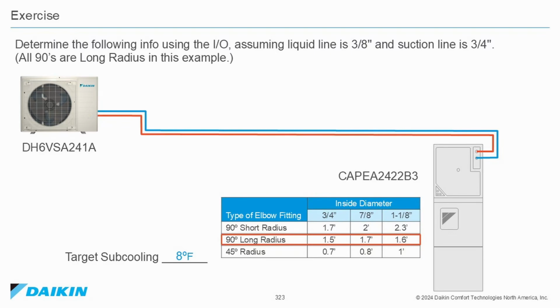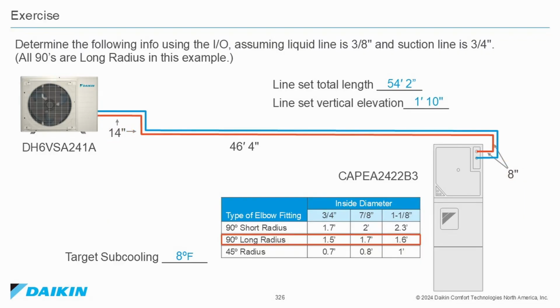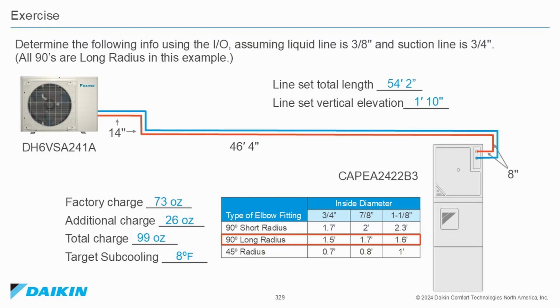Trying to reach a target subcooling of 8 degrees, we see here that our line set total length is 54 feet 2 inches. The line set vertical elevation, you'll see 14 inches vertical on the liquid line at the outdoor unit, and another 8-inch vertical difference on the liquid line going into the indoor unit, for a total of 22 inches, or 1 foot 10 inches. We can see in the I/O manual and on the outdoor unit data tag that the factory charge is 73 ounces. Using the chart that we had just looked at, we calculate the additional charge to be 26 ounces, which gives us a total charge of 99 ounces.